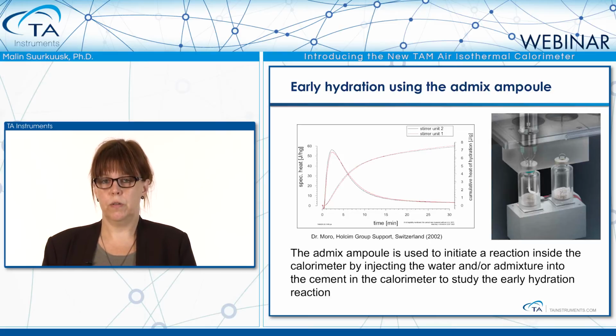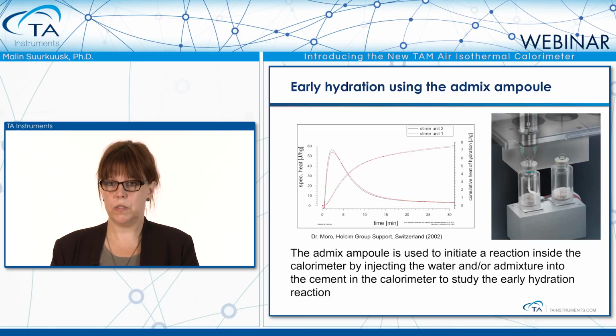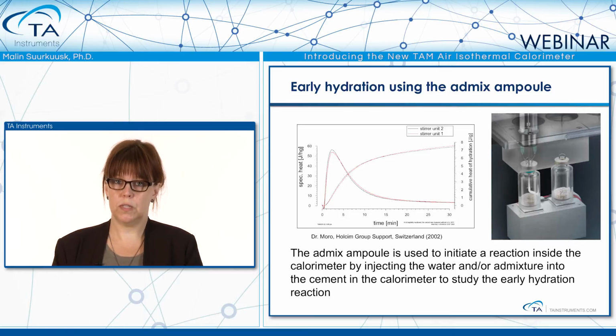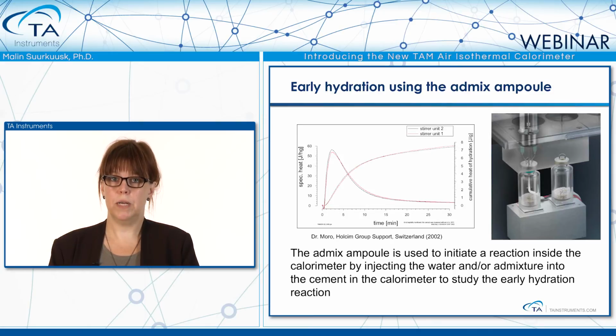For early hydration, if you're going to mix your cement sample outside for measuring 7 days of hydration, you can mix it in the ampoule and put it into the calorimeter, but then you miss the first 10, 20 or 30 minutes of the hydration process, depending on how high the signal is. If you're interested in this first signal, then you should use the admix ampoule. In the admix ampoule, you put your cement powder into the ampoule, and then you add water and mix it inside the calorimeter. You initiate the hydration reaction inside the calorimeter to be able to measure from the first injection of water. In the example here, you see 2 samples, and on the time scale, no, we're not on days, it's the first 30 minutes you're looking at here.